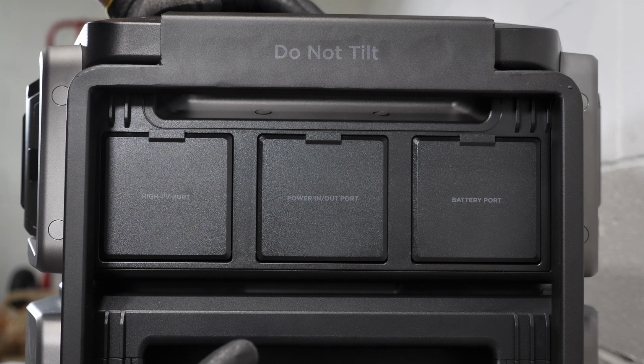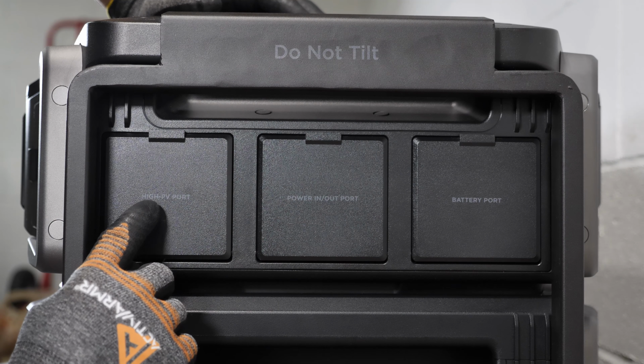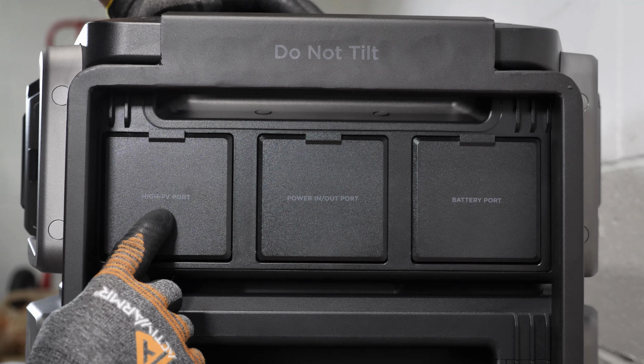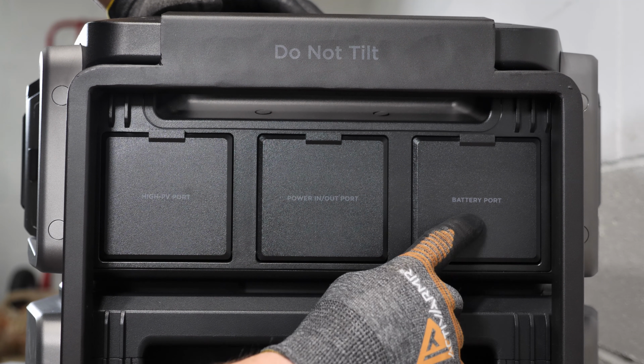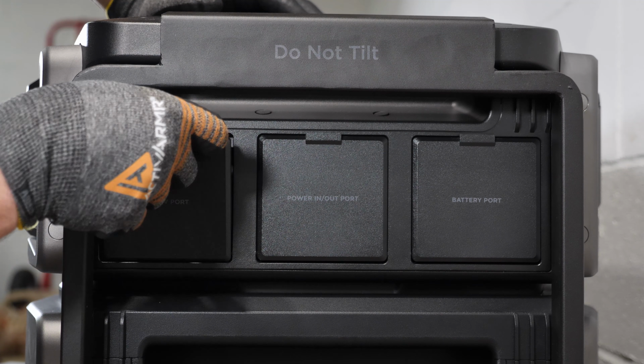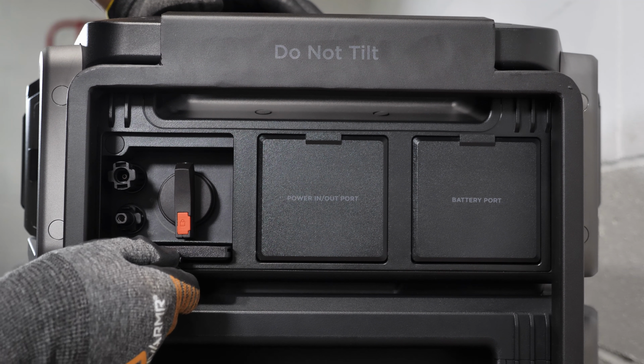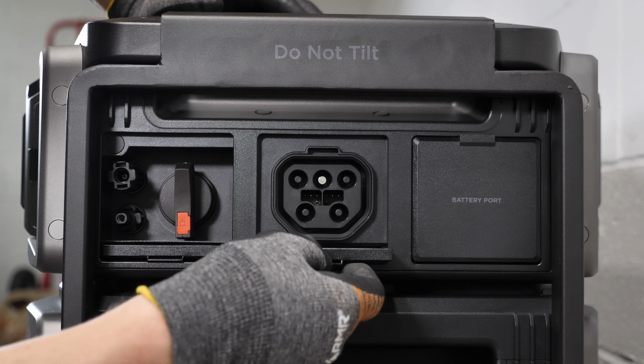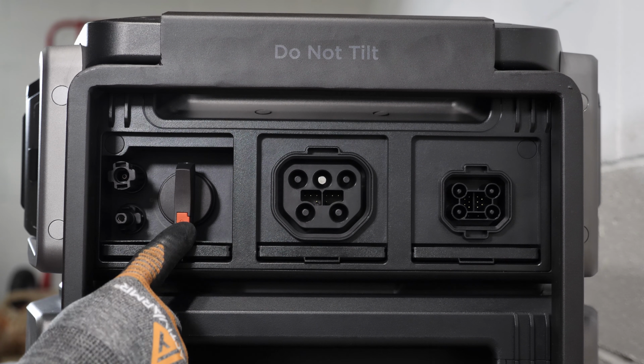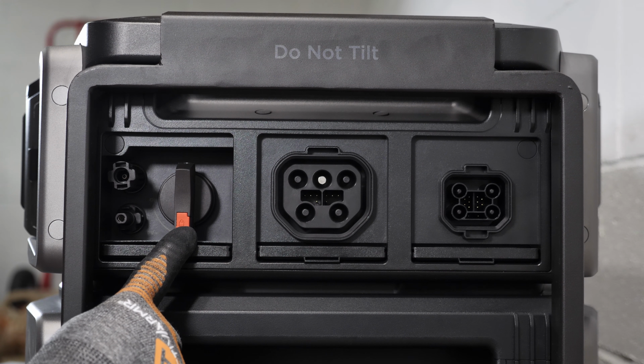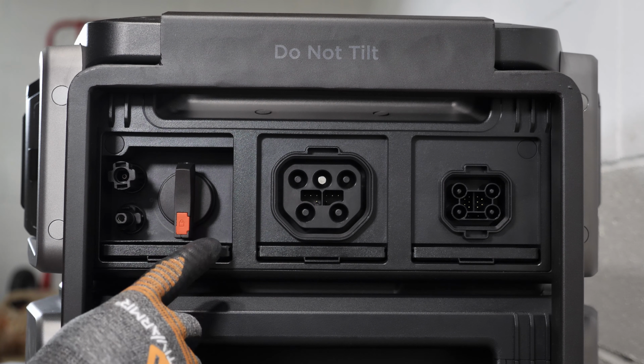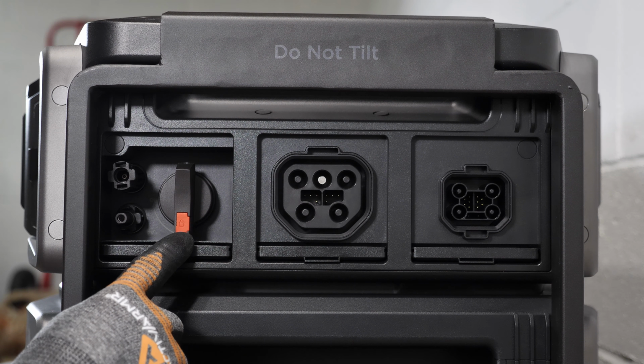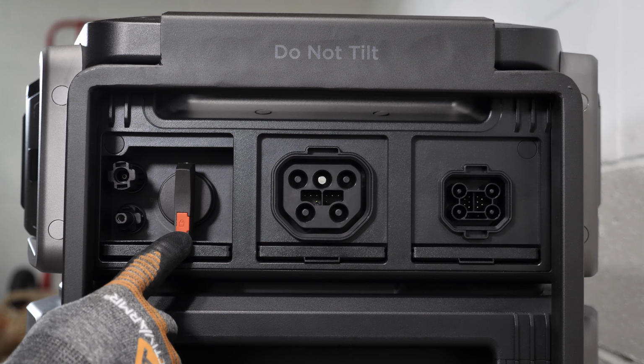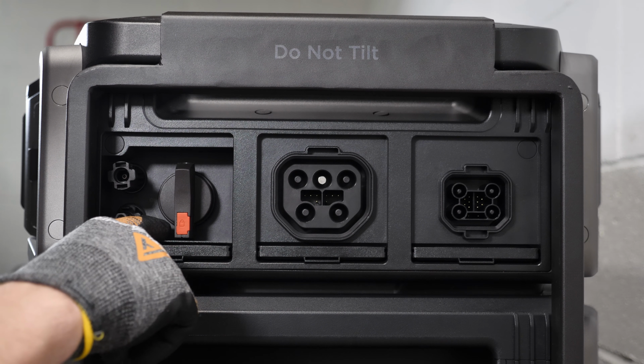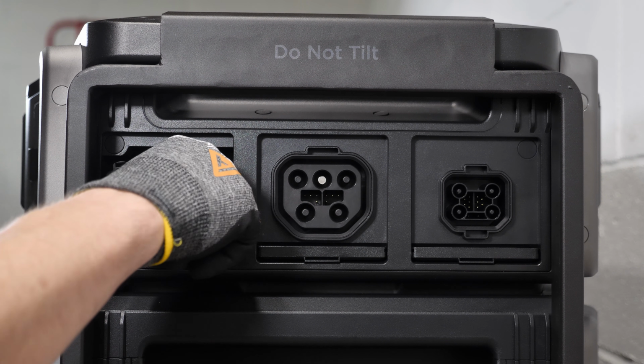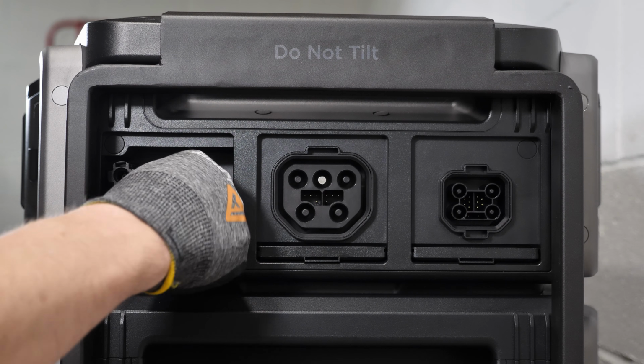This is the right side of the inverter, just above the battery. We have your high voltage PV port, power in and out port, and your battery expansion port. Same thing, these doors are magnetic and slide in to get out of your way. The voltage range here is 80 volts all the way up to 450 volts, 15 amps or 4,000 watts. That's freaking amazing. There's also a little spot where you can put a lock on there, so you can turn it on or off.